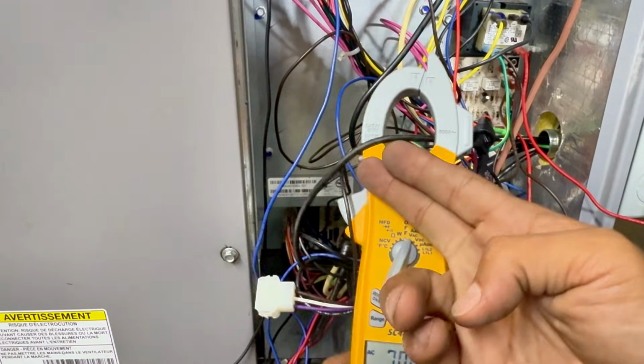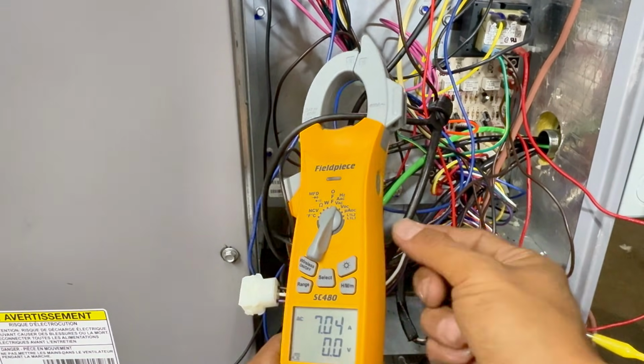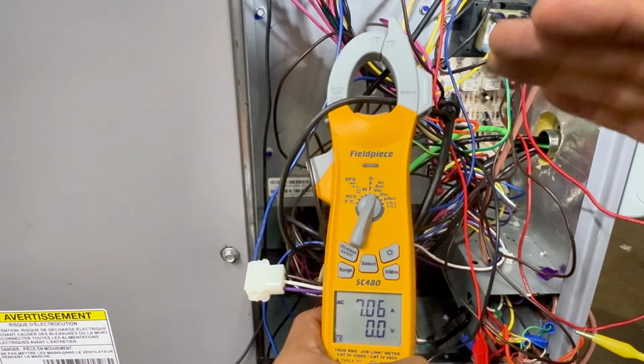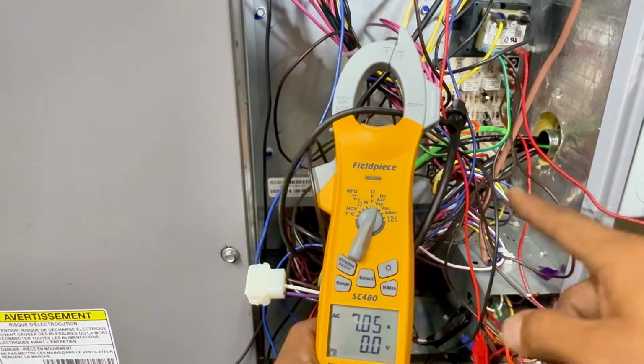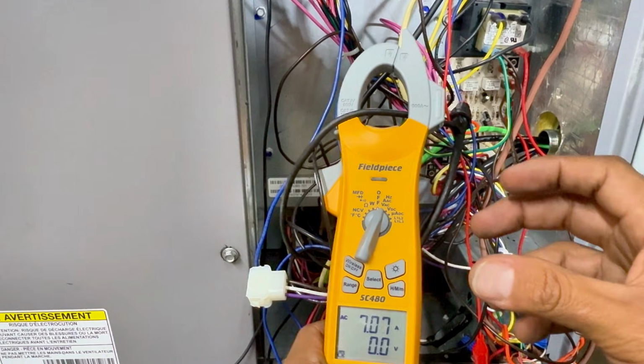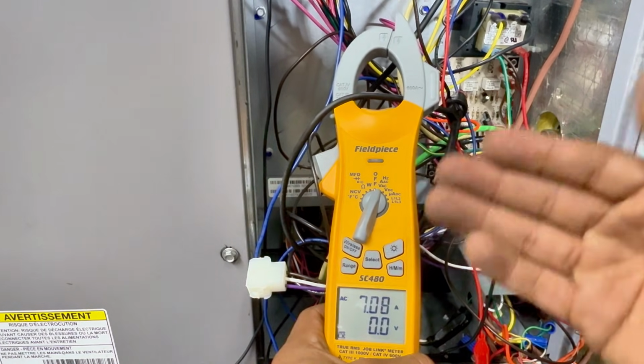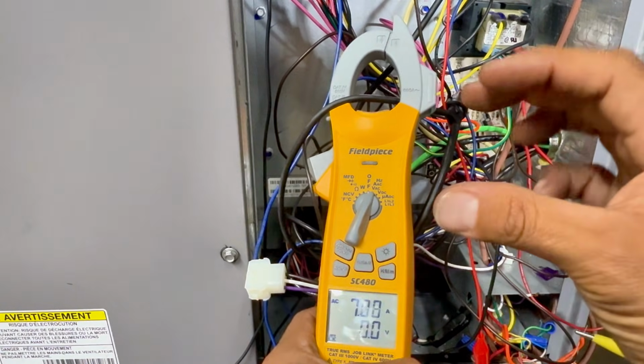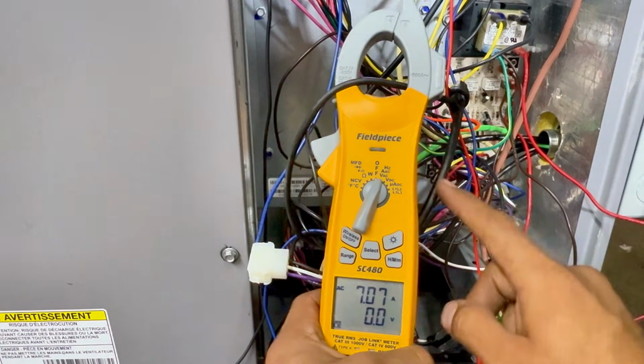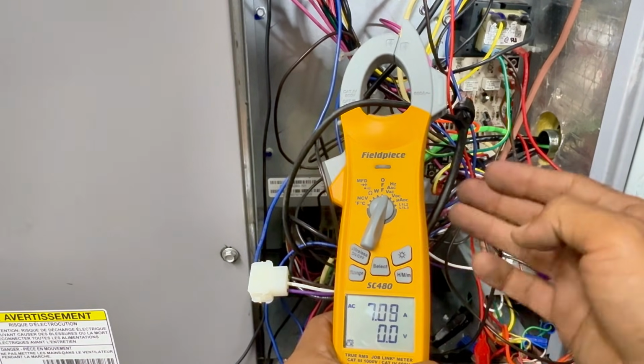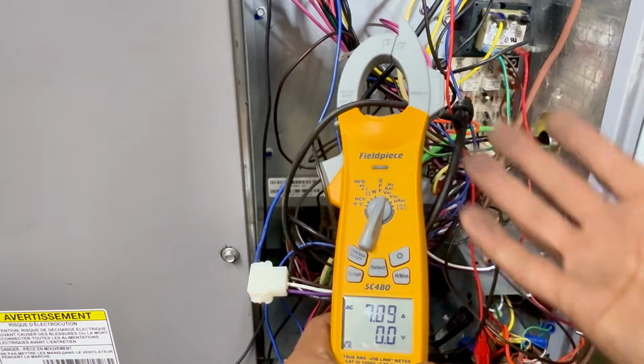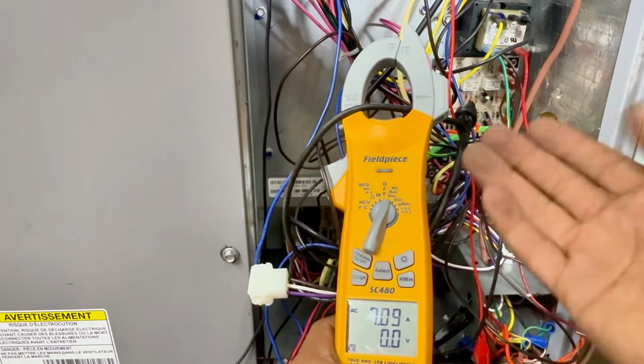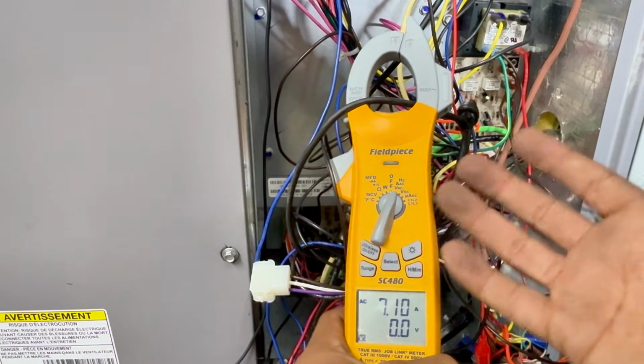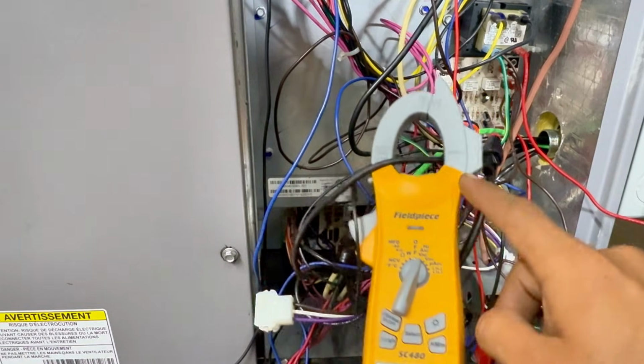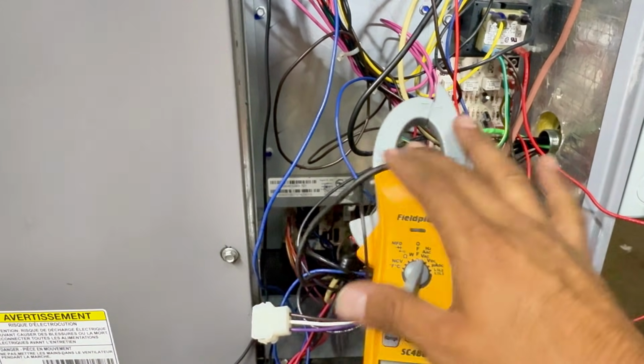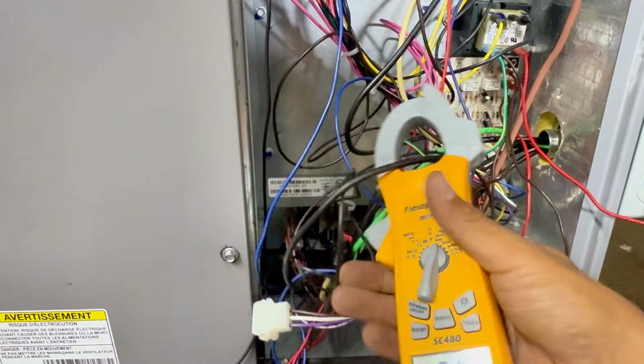And so this is why it's important when you're sizing the equipment, the thickness of the wire, right? The lower the number, the thicker it is. That unit here, it says you're gonna have something called max breaker size. If it says 50 or 60, you gotta put the wire according to that amp rating, right? So that's important too, right? If you go to a job and you know it's gonna pull 30 amps, you're gonna put in the 30 amp breaker, you better put in a 10 gauge wire, not a 12 gauge. So there's different codes for different cities and different things that you're working on, but I just wanted to show you how you can check amp draw by just checking one leg. It gives you the amp draw of all the loads of the system.